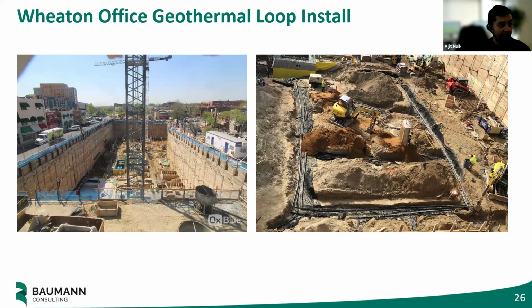Works well here, but you have to be really careful. Doing this type of thing creates more risk of scratches - there was a 10% limit, and there's slow crack growth that happens if it gets damaged. So it's really important there are testing and inspection protocols, which are in the IGBA specification. I think CSA 448 was the Canadian spec they adopted - don't quote me on that, but you can find it on the IGBA website. It's really important those procedures are followed so things can work.